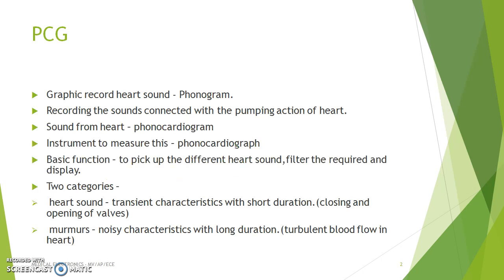What is PCG? The graphic record of the heart sounds is called a phonogram. Because the sound is from the heart, it is called a phonocardiogram. The instrument used to measure heart sound is called a phonocardiograph. This instrument uses a phonocatheter, a device similar to a conventional catheter with a microphone at its tip. The basic aim of the phonocardiogram is to pick up the different heart sounds, filter them out, and display or record them.